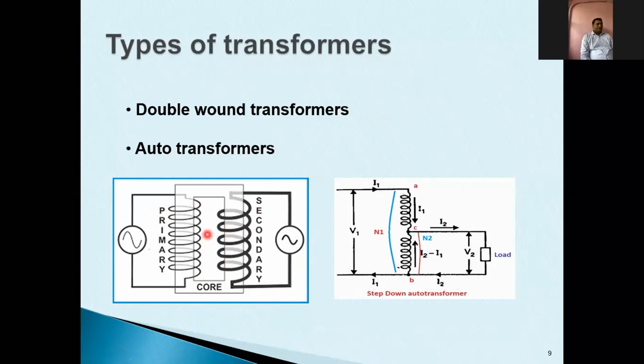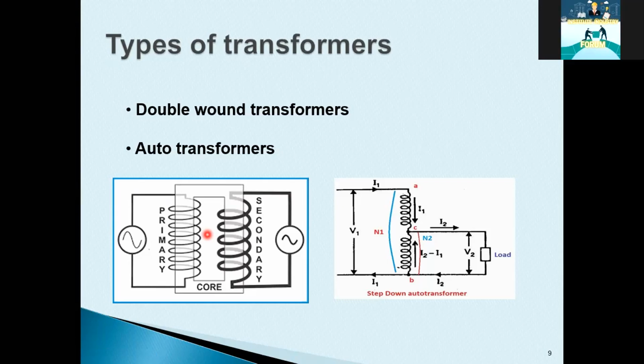Generally, in the recent past, we have not seen the air core transformer because of the development of CRGO or core material to reduce the reluctance of the circuit, or I will say the magnetic resistance of the circuit. And there is another type called auto transformers. When your voltage ratios are less, I will say in the range of 1.1 or 1.2, like you are just changing the voltage from 400 kV to 765 kV or 220 kV to 400 kV, in such case we do not have separate windings. We manage with the single winding to save the copper.